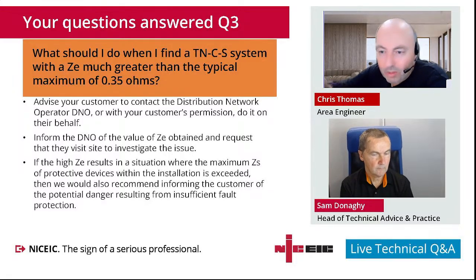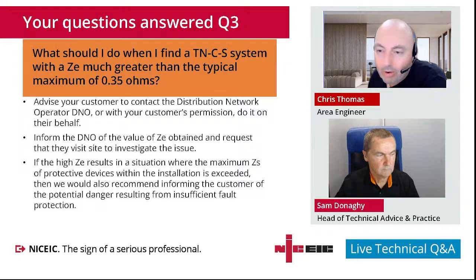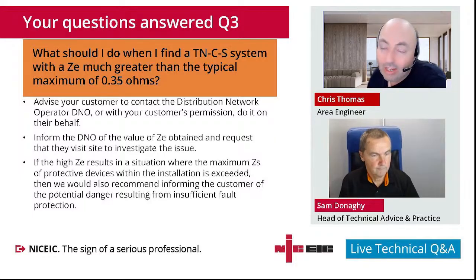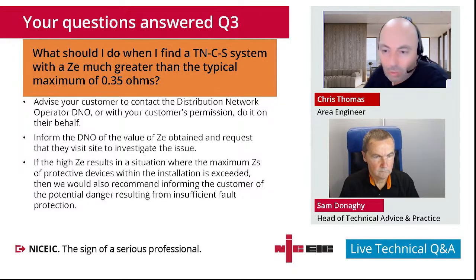you could have any of those earthing systems with either value. You need to conduct an investigation to make sure you are actually dealing with the correct earthing system. So the value doesn't always necessarily dictate what the earthing system is. These are just industry practices that we use to get a decent reading and stay within certain norms for any of the power systems that we work on. So if you've got a TN-C-S system, you could in theory have 0.35 ohms, you could have any value. So it's just to stress that it's not indicative of it being definitely one type of earthing system or the other. Further investigation and inspection will be required to determine that.